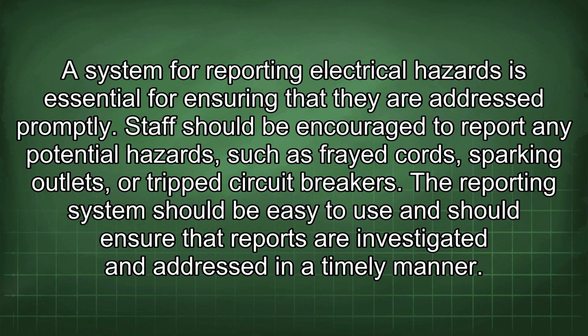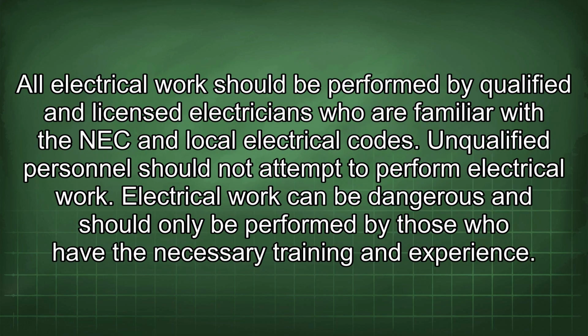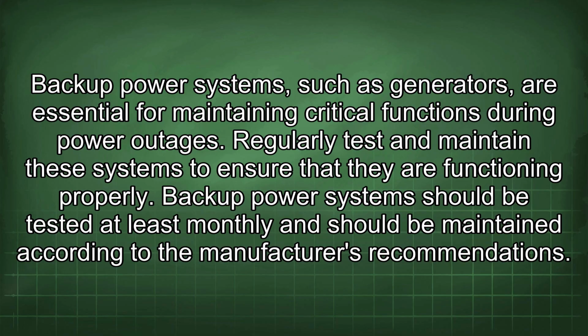The reporting system should be easy to use and should ensure that reports are investigated and addressed in a timely manner. All electrical work should be performed by qualified and licensed electricians who are familiar with the NEC and local electrical codes. Unqualified personnel should not attempt to perform electrical work. Electrical work can be dangerous and should only be performed by those who have the necessary training and experience. Backup power systems, such as generators, are essential for maintaining critical functions during power outages. Regularly test and maintain these systems to ensure that they are functioning properly. Backup power systems should be tested at least monthly and should be maintained according to the manufacturer's recommendations.